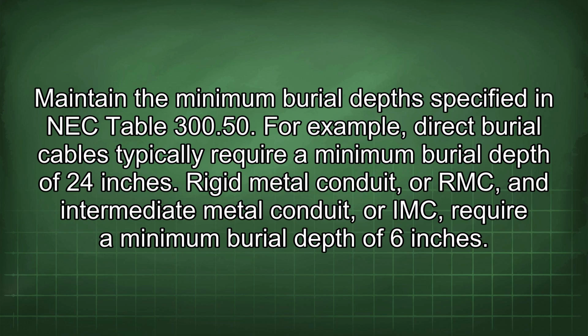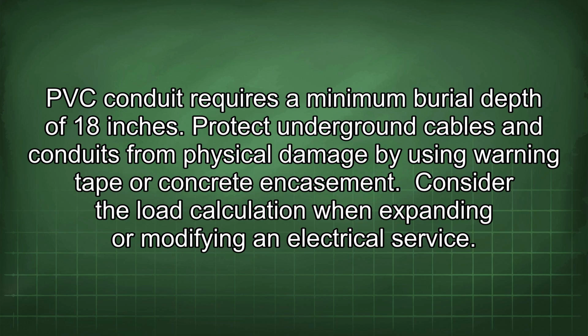When trenching for underground wiring, follow NEC guidelines and local regulations. Maintain the minimum burial depth specified in NEC Table 300.5. For example, direct burial cables typically require a minimum burial depth of 24 inches. Rigid metal conduit, or RMC, and intermediate metal conduit, or IMC, require a minimum burial depth of 6 inches. PVC conduit requires a minimum burial depth of 18 inches. Protect underground cables and conduits from physical damage by using warning tape or concrete encasement.